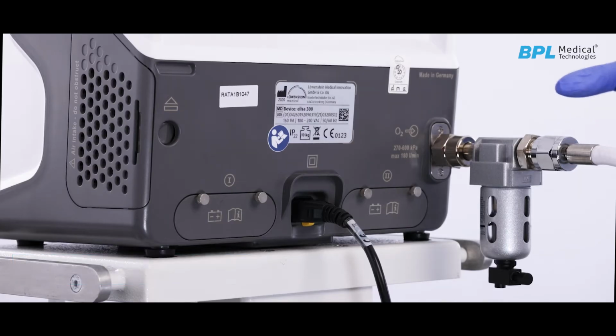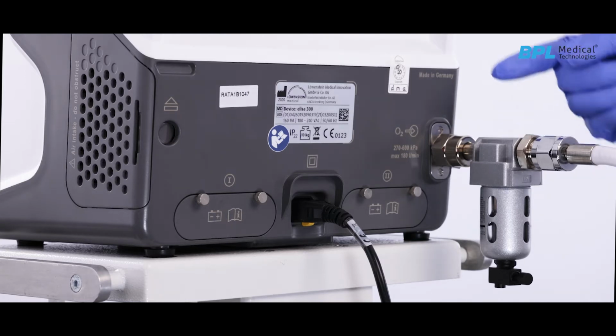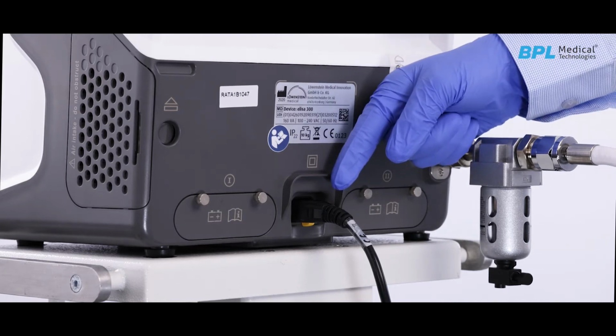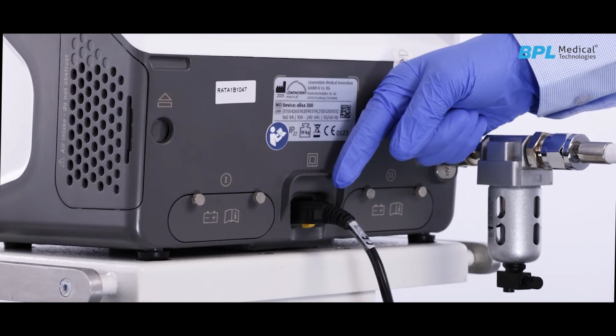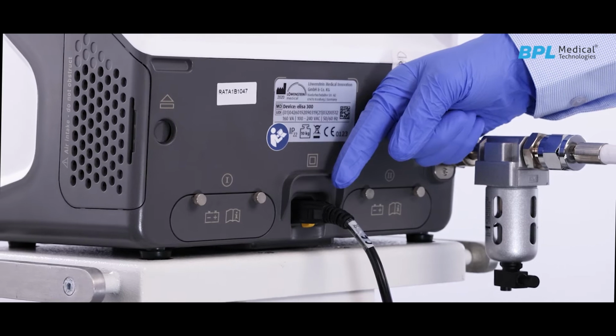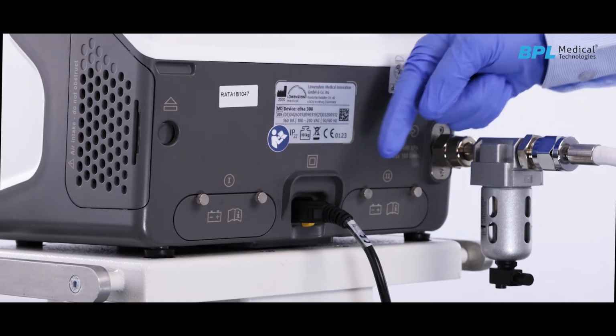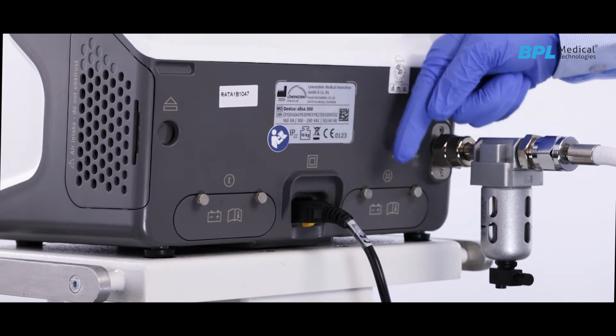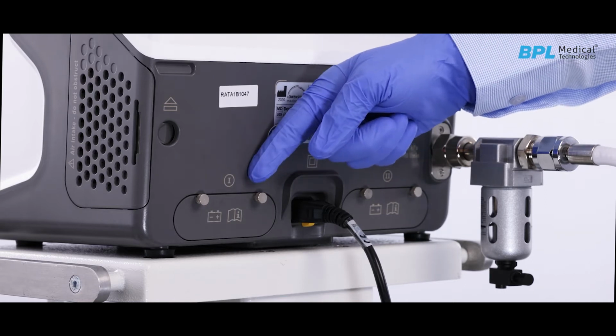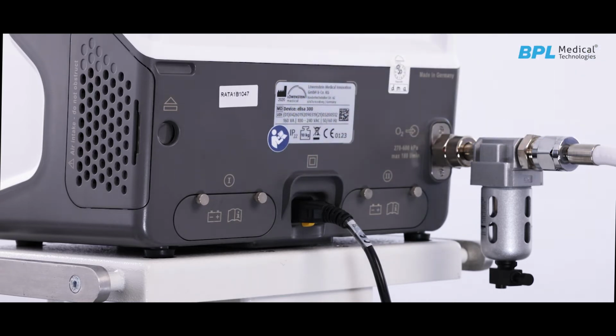Gas supply connection. ELISA 300 can be connected to the central oxygen gas outlets. High-pressure color-coded hoses supply standard oxygen. Power cord connection. A 2-meter long 2-pin power cord provides easy reach of the power plug source. Battery compartment. A hot-swappable 2-battery compartment enables longer backup time, supplied with lithium batteries. Its backup time is 2 hours on a fully charged battery.